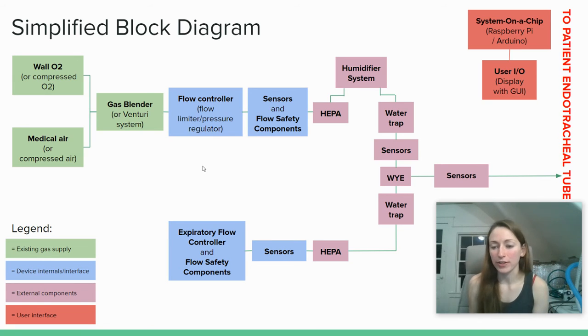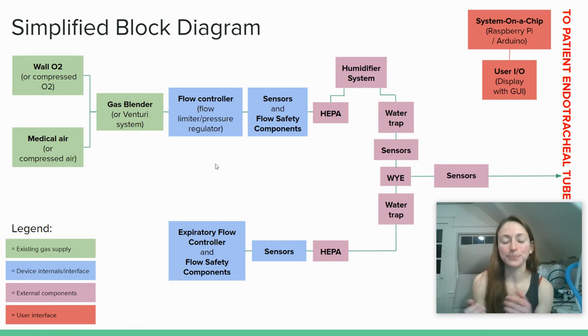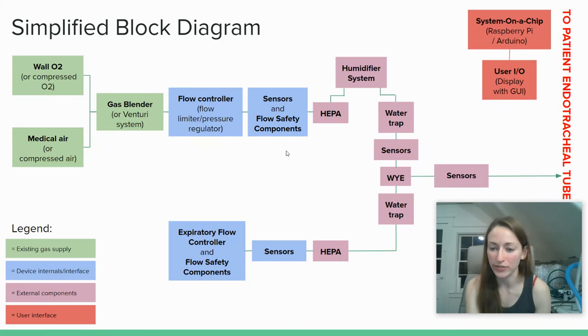This may involve a proportional valve, solenoids, other types of valves. It may involve a mass flow controller, but in some sense we need a flow limiter and a pressure regulator usually. Downstream of this we have sensors as well as flow safety components. That's things like the pressure release valves if you're following a regulator. And then we move outside of the device, moving towards the respiratory circuit.